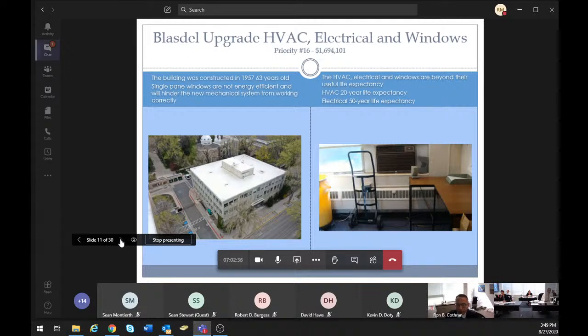There are 20 amp breakers in the building. The max capacity of a 20 amp breaker is 16 amps, or 80%. The building occupants consistently overload the circuits and trip the breakers. When the breaker is tripped, it's because there's too much current draw on the system, which can produce heat through the wire. If the breaker does not trip properly, it will cause the wire to overheat and catch on fire. This building's electrical system has surpassed its life expectancy of 50 years and needs to be replaced.